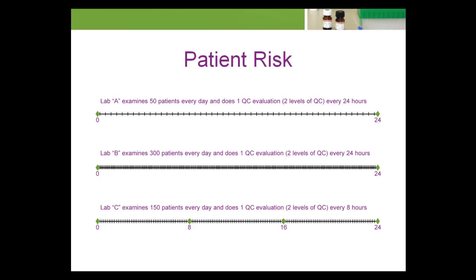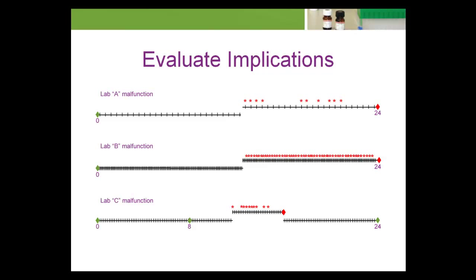To evaluate the implications of these QC strategy design decisions, let's look at what happens when the test systems malfunction in a non-obvious manner in the middle of the day. There is little risk in an obvious malfunction producing unreliable results; it is the unrecognized malfunction that increases patient risk. A shift in results can be difficult to detect prior to a QC event because the true patient concentrations are unknown. This illustration depicts a malfunction that shifts results higher to the extent that there is a 40% chance that the examination error in an individual patient result is large enough to make the result unreliable, exceeding the allowable total error. Each red asterisk represents an unreliable patient result produced due to the unrecognized malfunction.